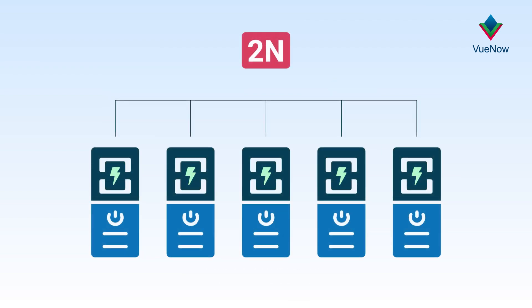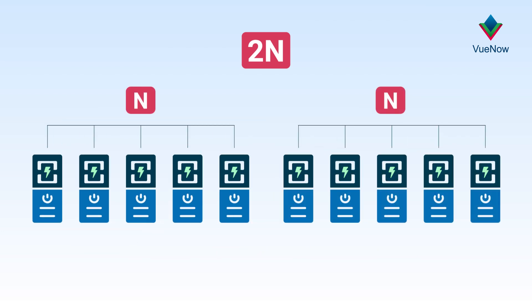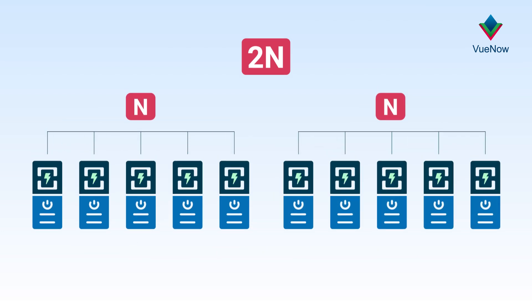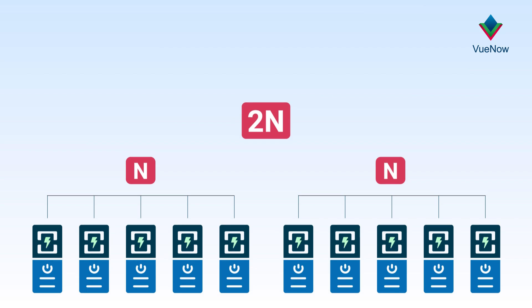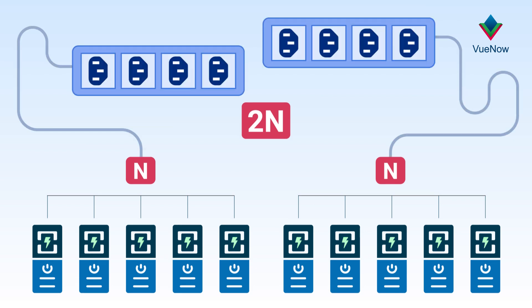2N mirrors the original setup. So if a datacenter had 5 UPS units, 2N redundancy would be 5 more UPS for a total of 10 UPS. This would also have 2 separate distribution systems, so in an unfortunate event it could switch over without a problem.